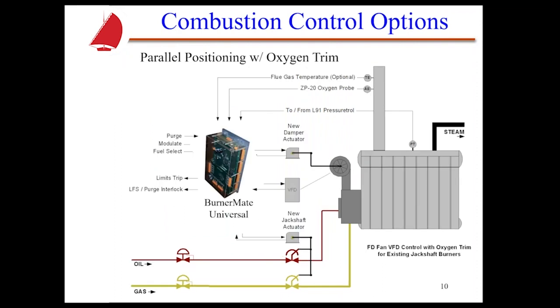Now, when we go to parallel positioning, we basically have now our servos mounted directly on the air damper. You have servos mounted directly on the oil valve, the gas valve, and we could even be operating a variable speed drive. We could even be operating a flue gas recirculation damper. So all of those can be operated directly. In the case of our FlexFit product, which is our least expensive parallel positioning system, it can even do damper actuation control also. So we can do draft control. So we have a lot more flexibility with these new controls because we have these outputs to drive these servos, and we're not relying on some type of linkage, if you will, to operate those valves.